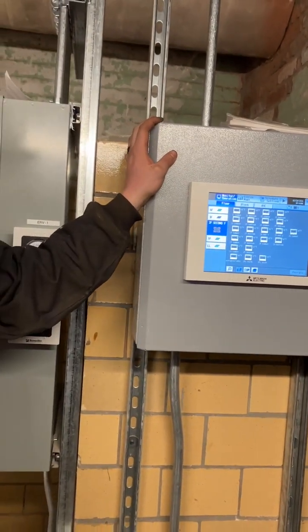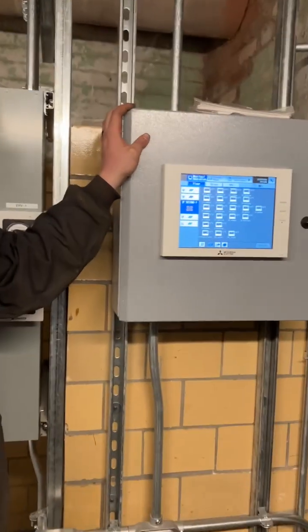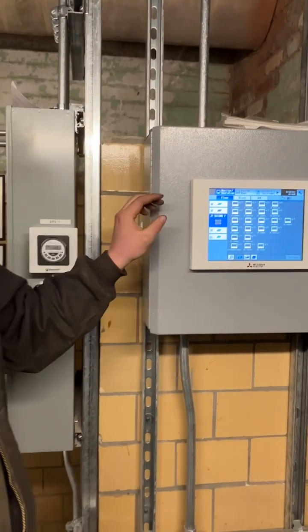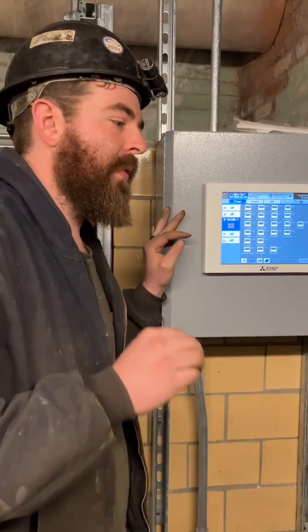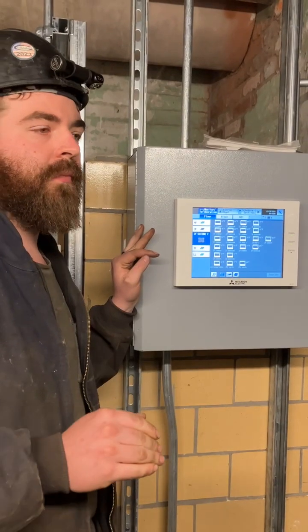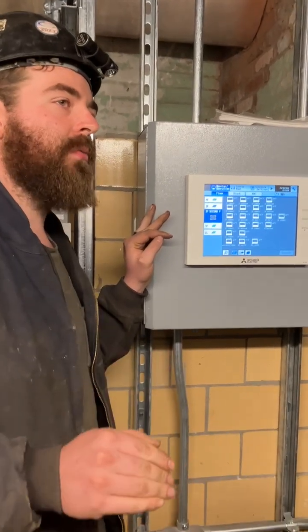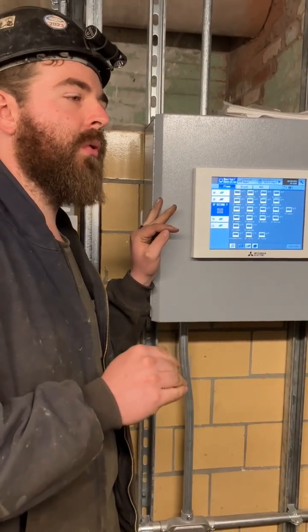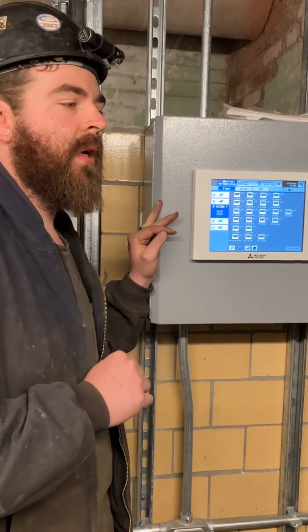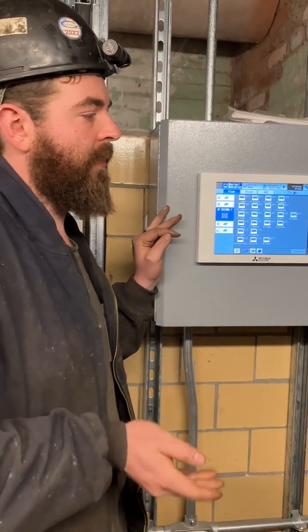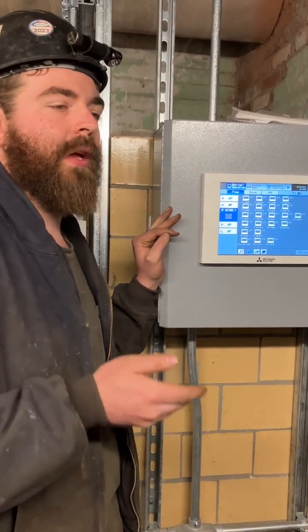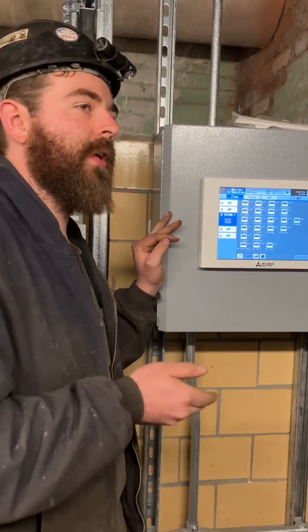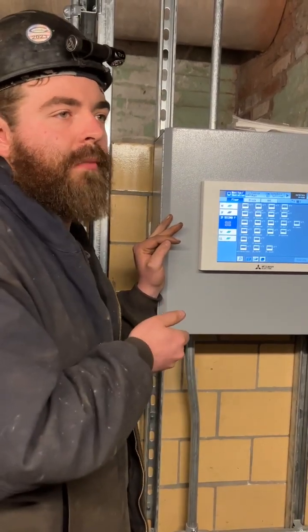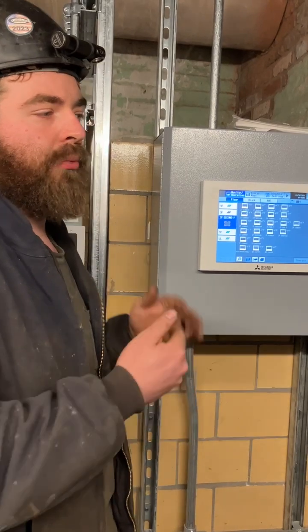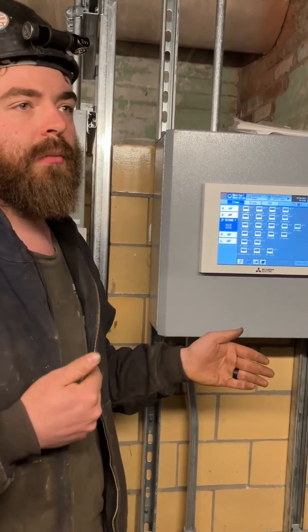So these are doing heat and AC, right? So these have the capability to do heat and AC. Yep, again that's being commanded through the Pelican system. Each unit has baseboard as well as 2 or 3 VRF units. So the most effective, efficient way of design is to have the baseboard really do almost all of the heating, and these would be just like an emergency backup. The easiest way to break the two is through the Pelican system.